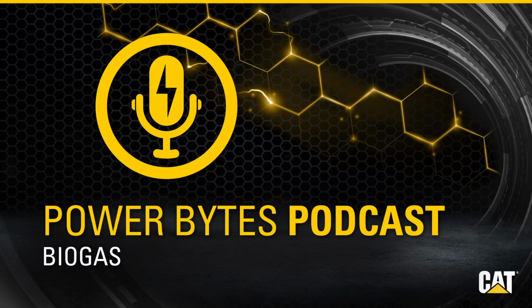In regard to the genset and the CHP system, the key consideration relates to the corrosive nature of the gas, which makes it a very tough and pretty challenging application for any machine. We provide guidelines on gas quality and list substances and properties of the gas which have to be maintained to ensure proper operation. This also helps the plant operator select and size the necessary treatment for the biogas.